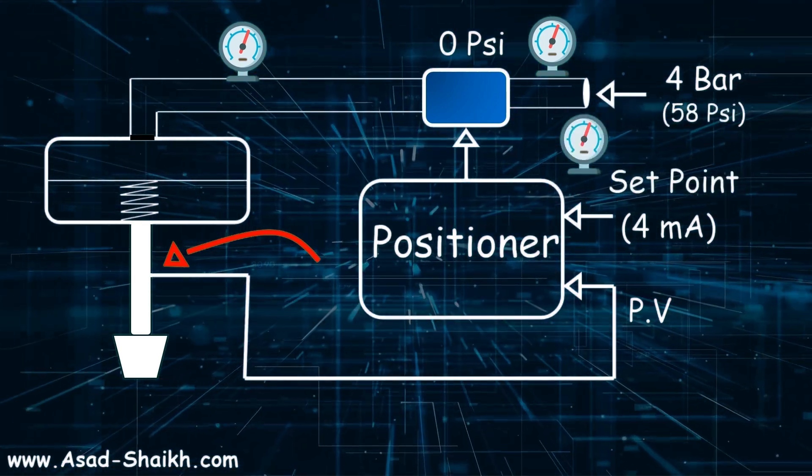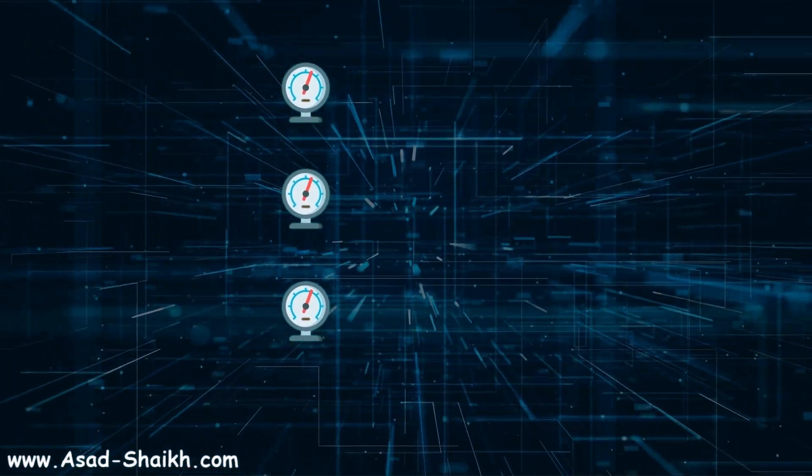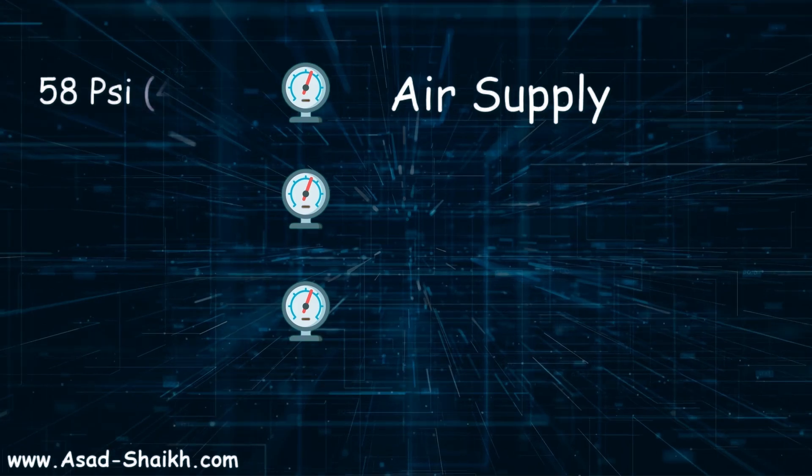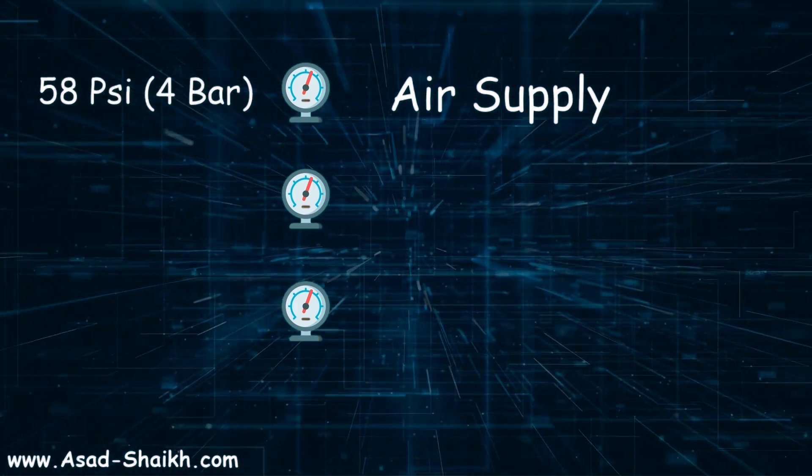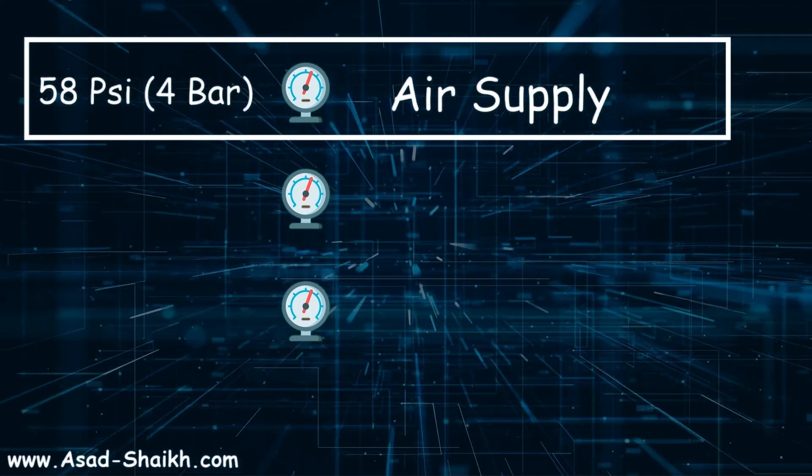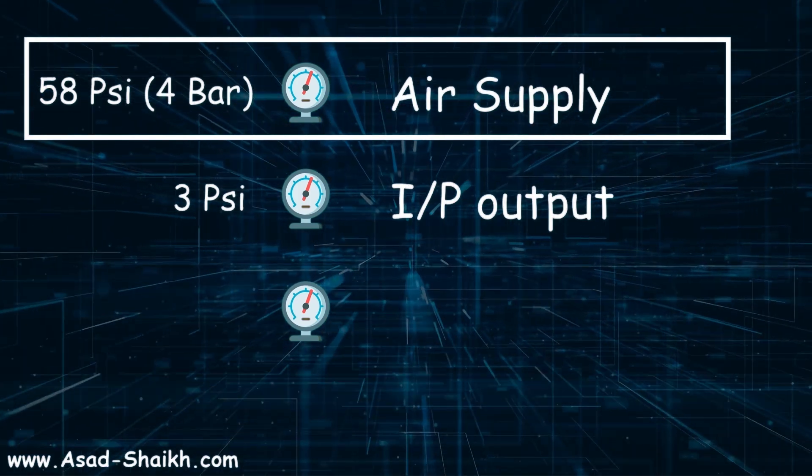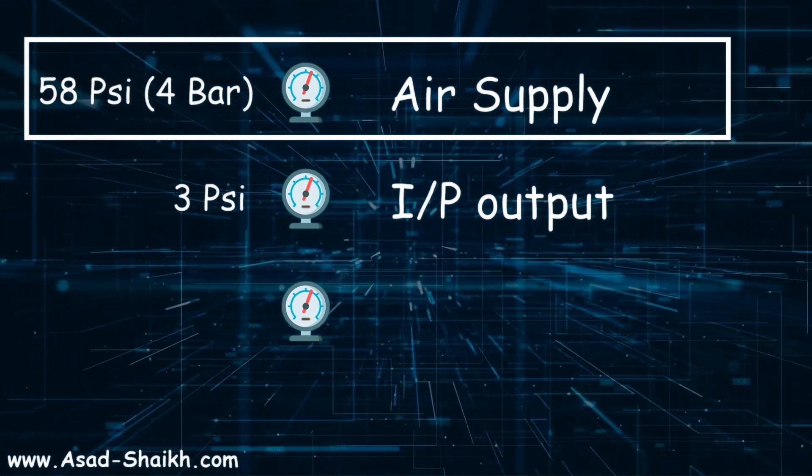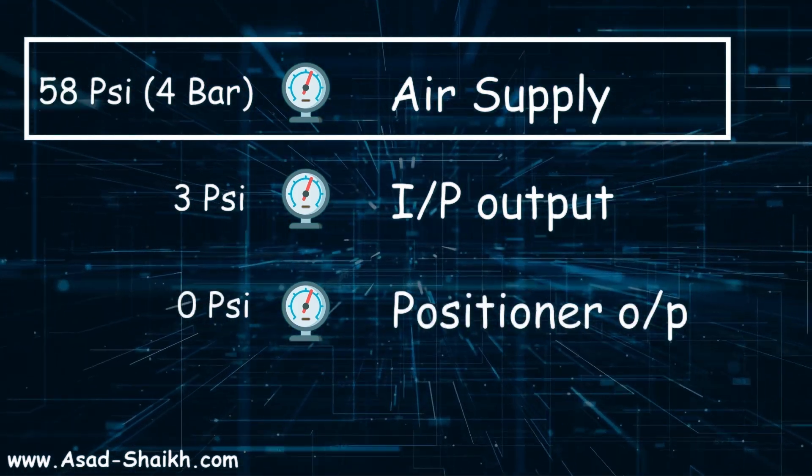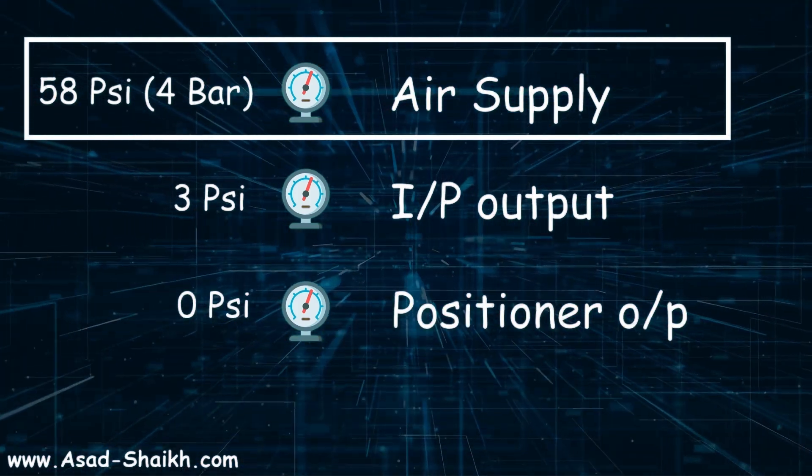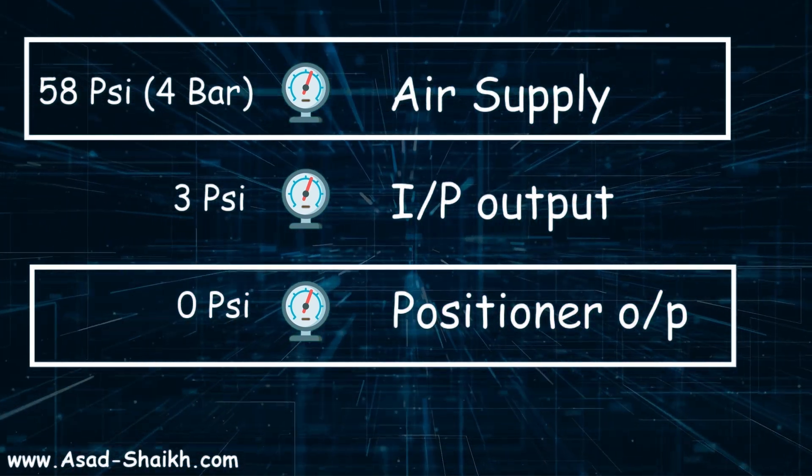Let us try to understand how this will help you. You get to the plant and you realize your control valve is not working. The first thing you check is, is the air supply proper? If the first gauge is showing you 58 psi or 4 bar, that means the air supply is good enough. Then you check, is the I/P working or not? For example, if the output shown is 3 psi for a 4 milliampere signal, that means your I/P is working properly. Then you get to the third point: is the positioner giving the correct output or not? And that is how you can troubleshoot a lot of issues that can happen in any control valve.